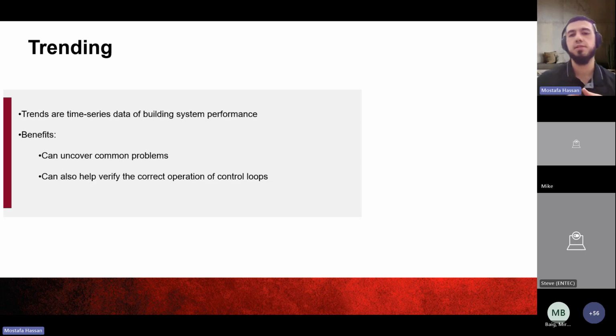You can identify inefficiencies like simultaneous heating and cooling, right? You don't want your air handling unit to be going into both those modes at the same time, or your building is asking for heating or cooling at the same time, which doesn't make sense, depending on the weather outside, right? Or you can optimize system performance, right? By understanding how those building systems perform over time, operators can make adjustments, right? And you can improve the efficiency and comfort, for instance.